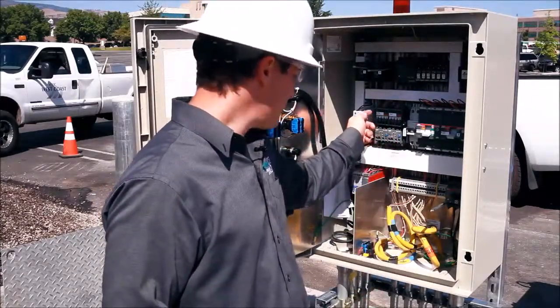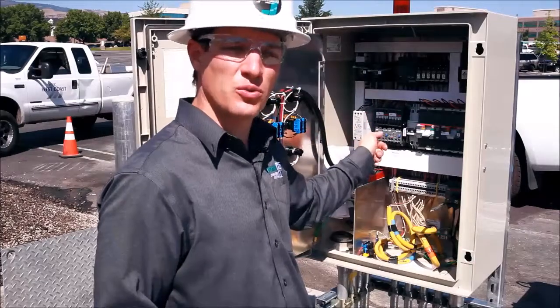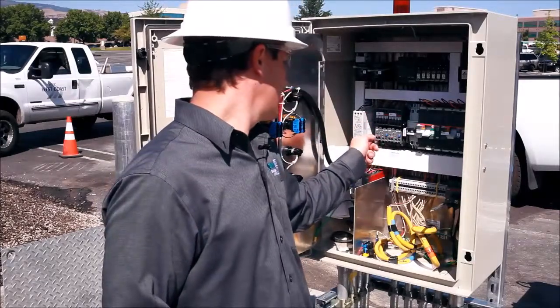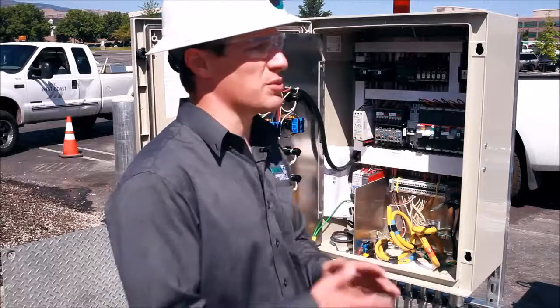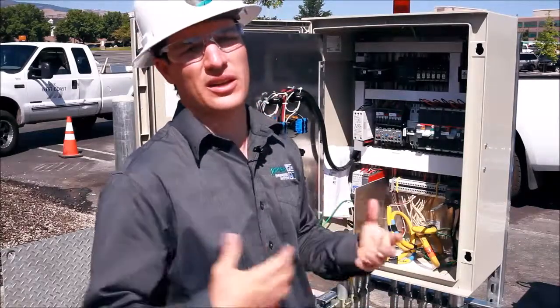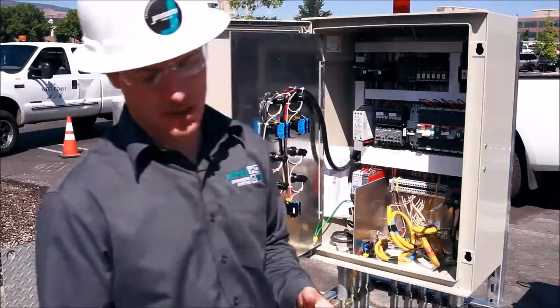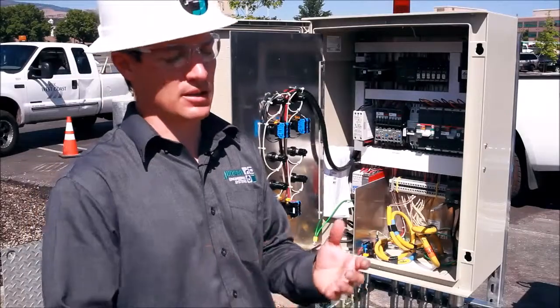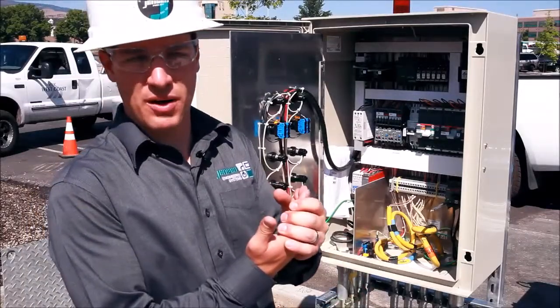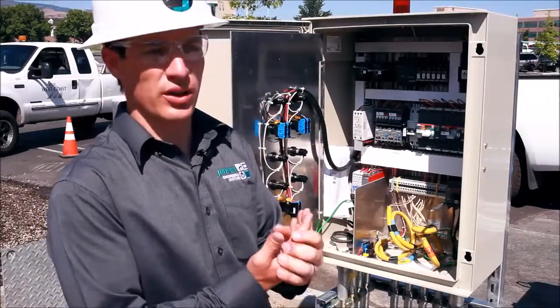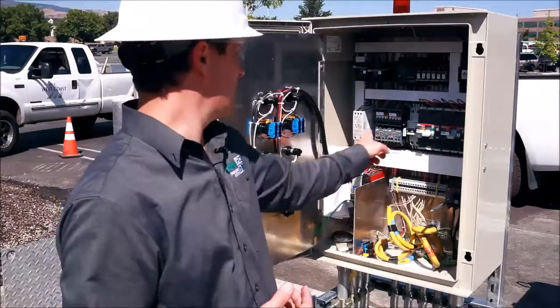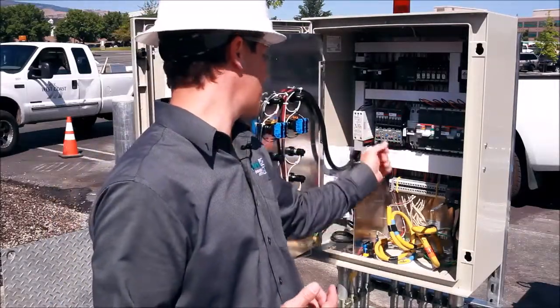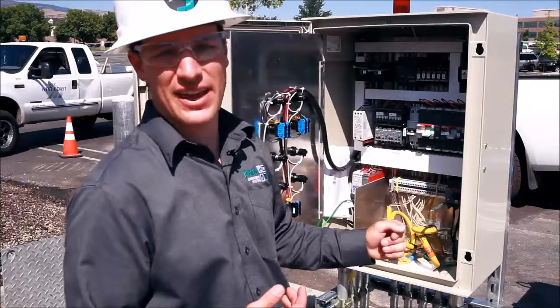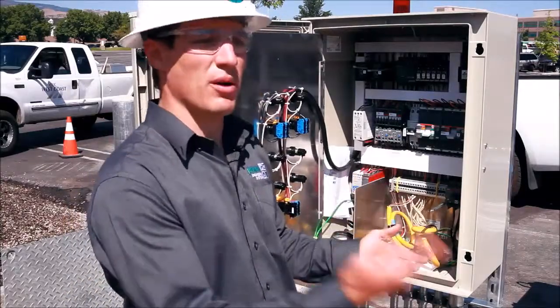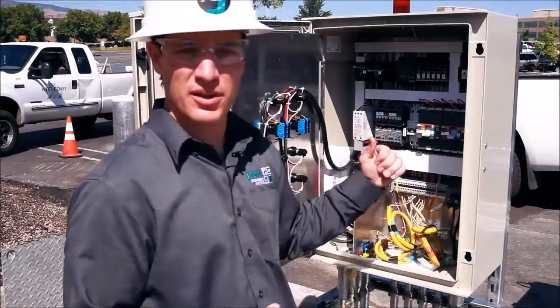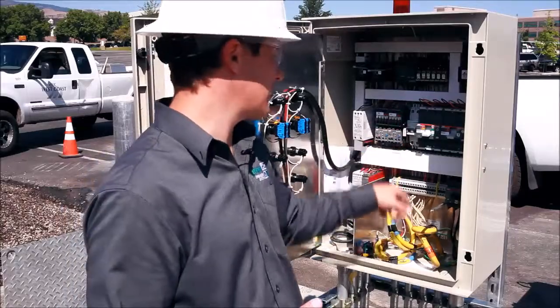From there, the power passes to the overload relays. The overload relays protect the motor from any high current draw. So if there was some type of impediment preventing the pump from rotating and the pumps were pulling high amps, so right now we're set at about 5.5 amps, anything above 5.5 amps is going to pop the overload relays and prevent the power from getting down.